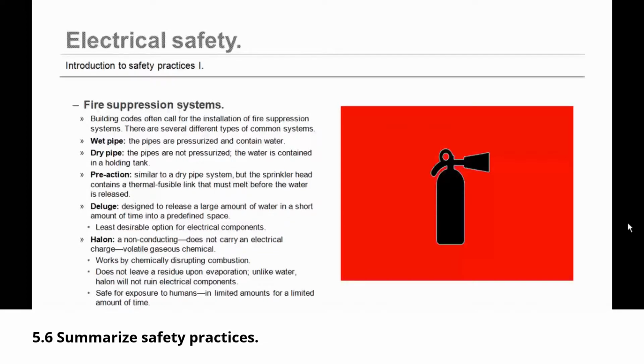Building codes often call for the installation of fire suppression systems, and there are several different types of common systems. There's the wet pipe. The overhead pipes are pressurized and contain water all of the time. Then there's the dry pipe. The pipes are not pressurized. The water is contained in a holding tank until a fire breaks out, and then it is pumped to the area where it needs to be dispersed. There are pre-action types of fire suppression systems. They're similar to a dry pipe system, but the sprinkler head contains a thermal fusible link that must melt before the water is released. Then there's the deluge fire suppression system.